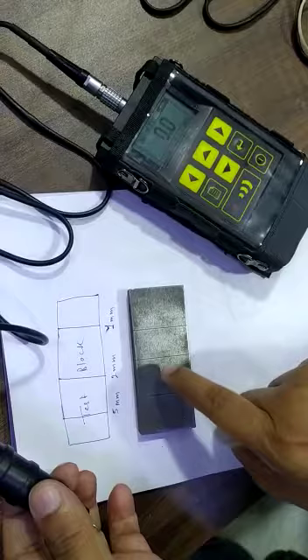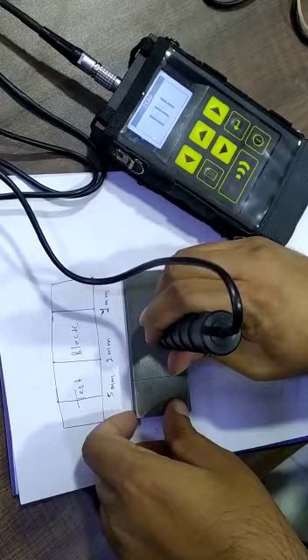We will first calibrate the machine near the crack where there is no crack, at the zero crack location. We came here. Some reading is coming. We will make it zero. Then again we will measure when there is no crack.